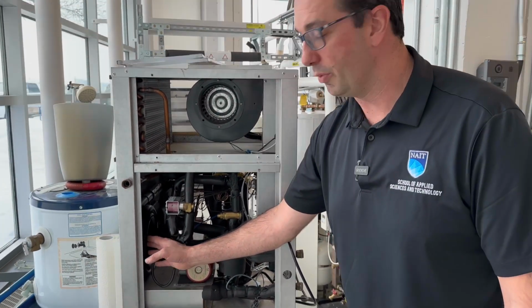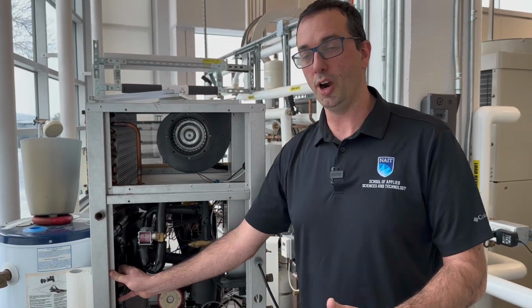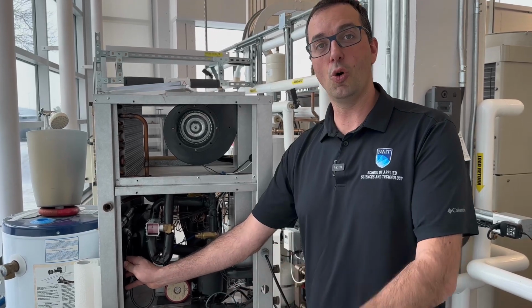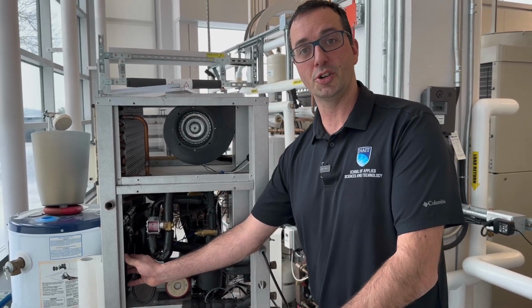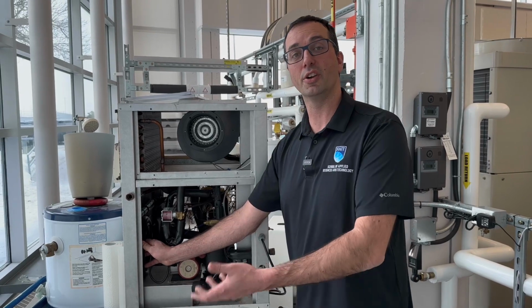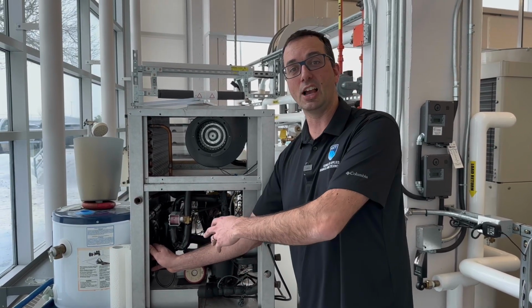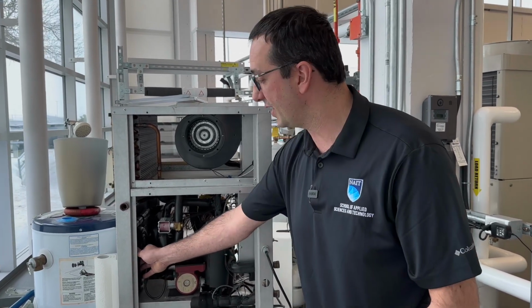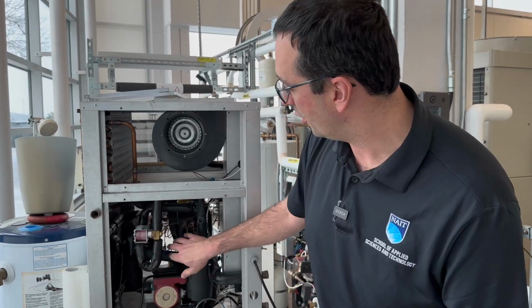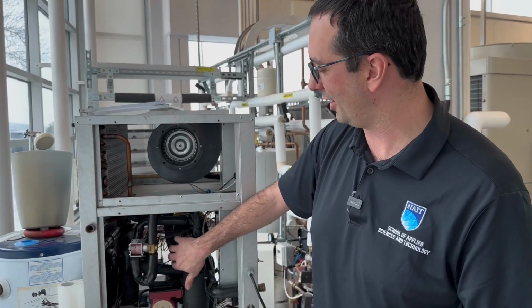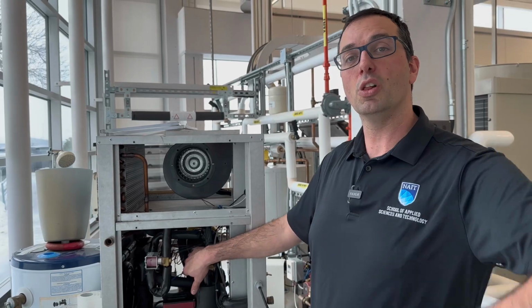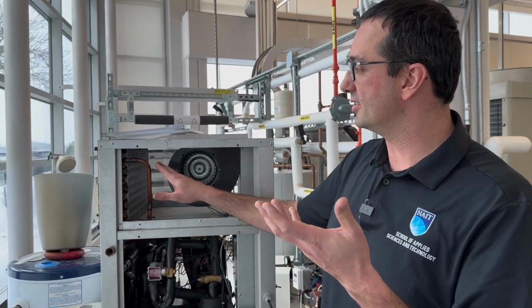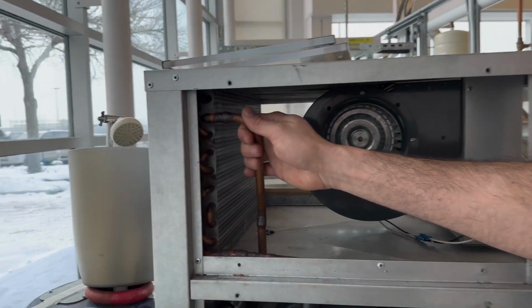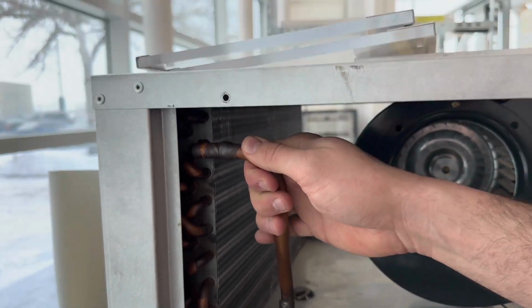This is a coaxial heat exchanger that takes energy from the water and puts it into a refrigerant. The refrigerant, just like before, would be at a temperature colder than this loop. Let's say the refrigerant's at minus 5 degrees Celsius and the water's at plus 5 - the water is actually heating up the refrigerant. Once we've gathered some energy from this water, we go through a compressor at the back that we can't quite see, and the compressor will upgrade that heat again and send the refrigerant up in this area, where this is our water-to-air heat exchanger.